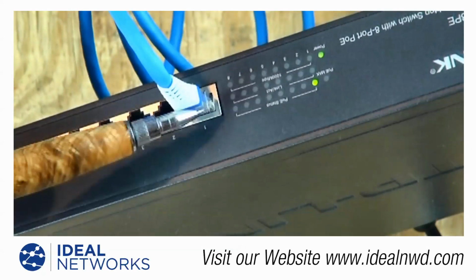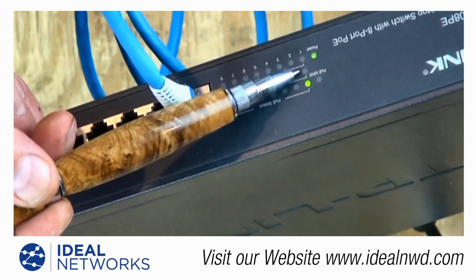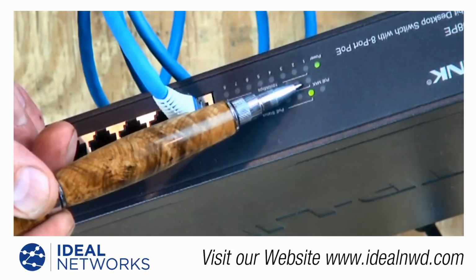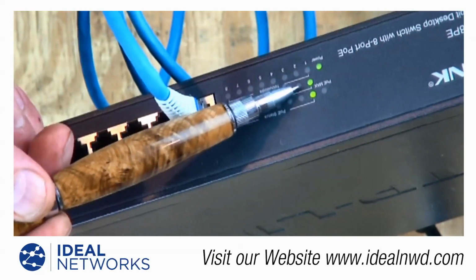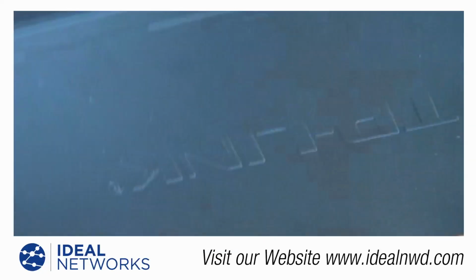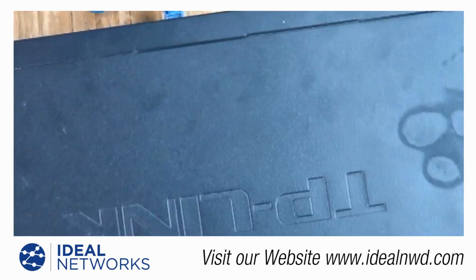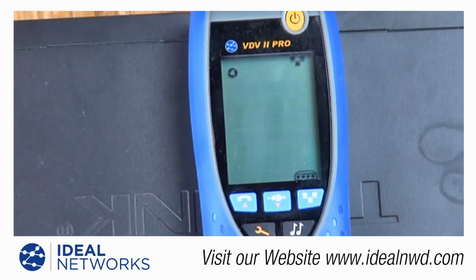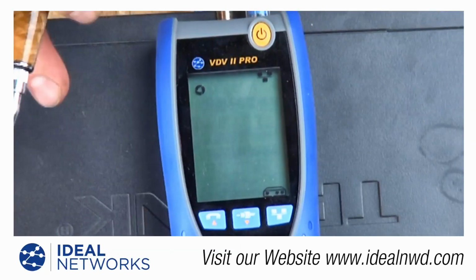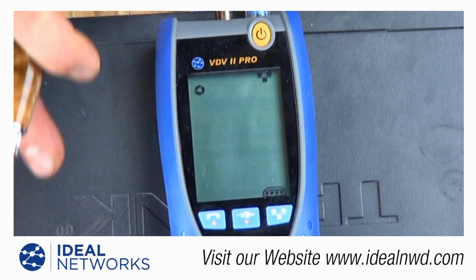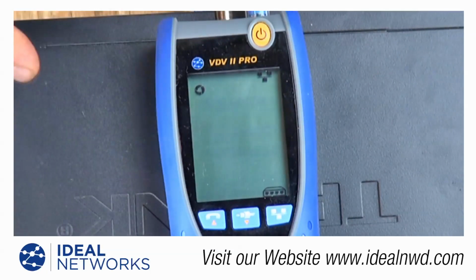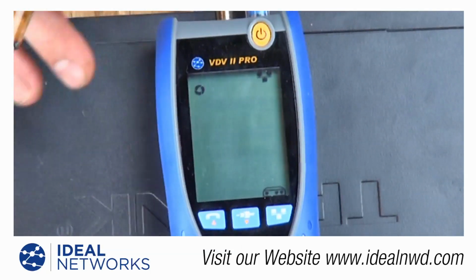I'm on port number 1, and sure enough, port number 1 is flashing on the switch, indicating it sees the tester on the other end of the cable. This is very helpful when troubleshooting and tracing wiring problems back to a switch. The hub blinking feature and the ability to sense active data networks is something you won't find in other wire mappers in this price range—it's a great feature technicians can really use in the field.